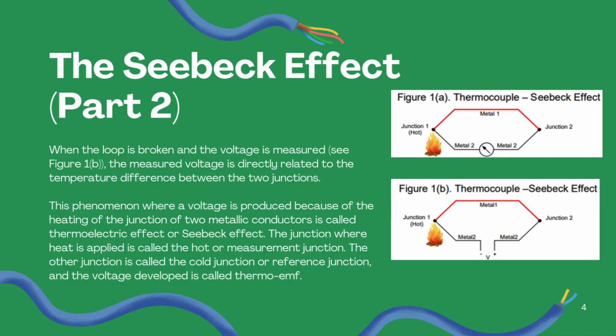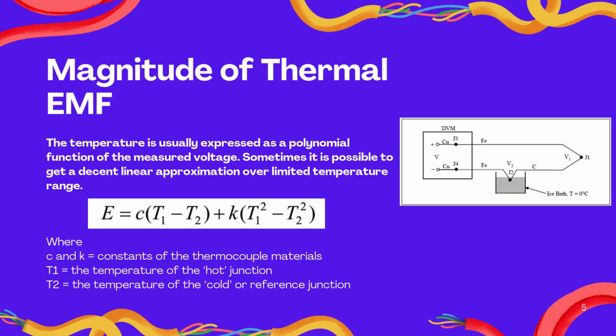This phenomenon where a voltage is produced because of the heating of the junction of two metallic conductors is called the thermoelectric effect or Seebeck effect. The junction where heat is applied is called the hot or measurement junction. The other junction is called the cold junction or reference junction. And the voltage developed is called thermo EMF. To calculate the thermal EMF, we can use the equation below. The temperature is usually expressed as a polynomial function of the measured voltage. Sometimes it is possible to get a decent linear approximation over a limited temperature range.